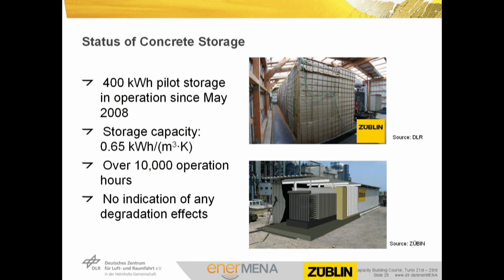Thermal energy storage using concrete as storage material has been demonstrated at pilot scale. A 400 kWh storage unit has been in operation since May 2008, with a storage capacity of 0.65 kWh per cubic meter per Kelvin. The pilot-scale unit has been operated for more than 10,000 hours with no indication of any degradation effects identified.